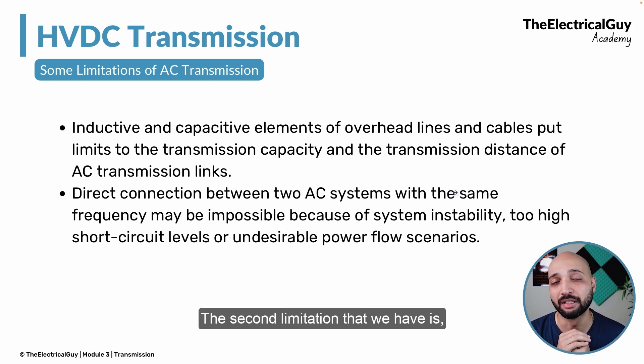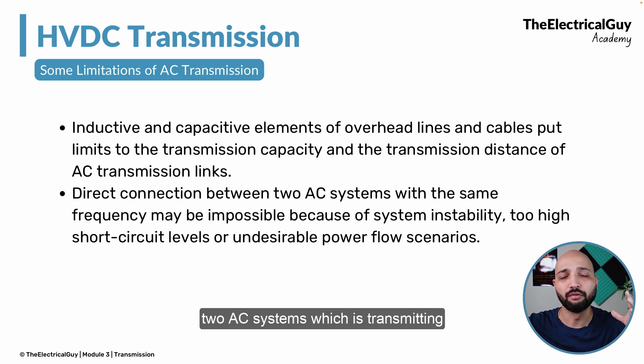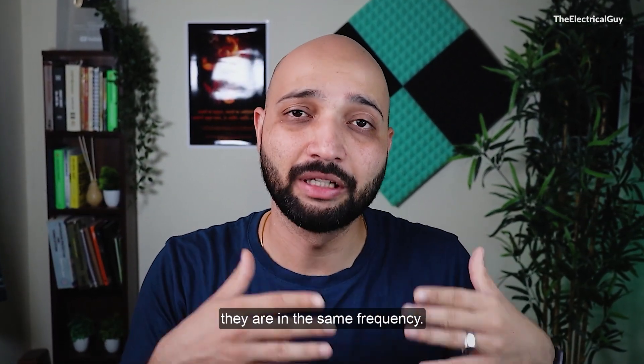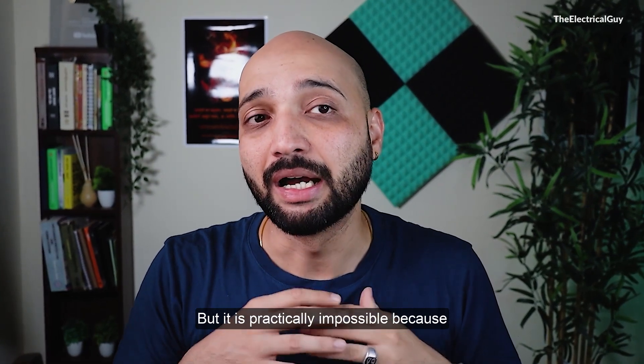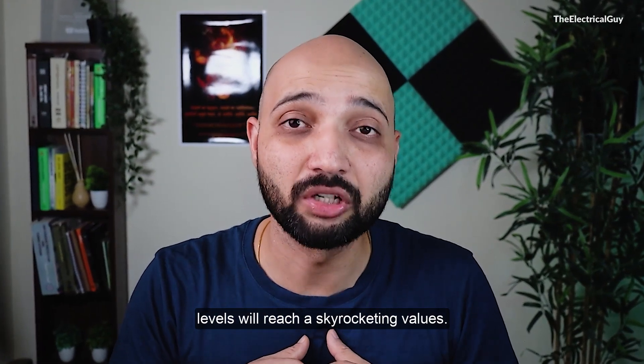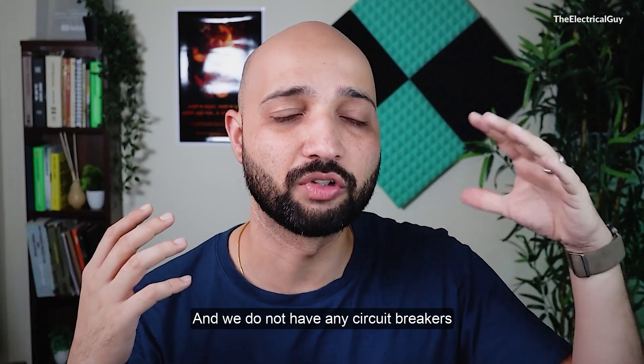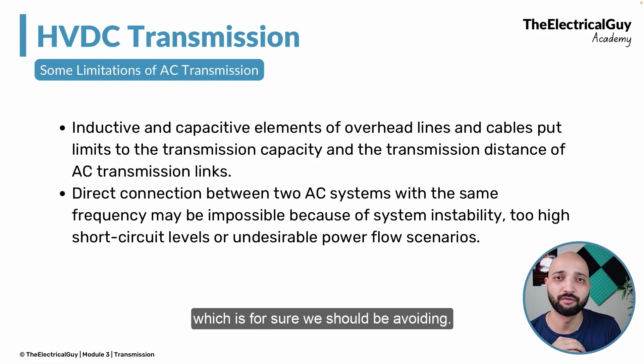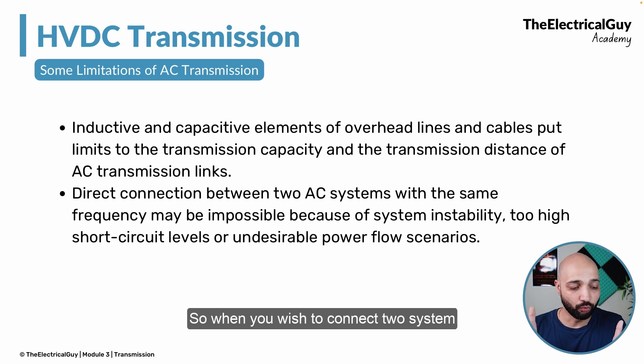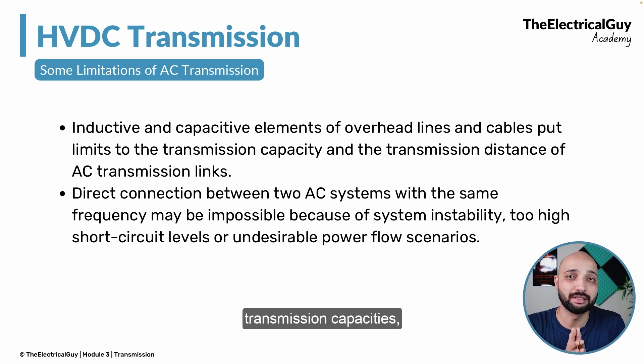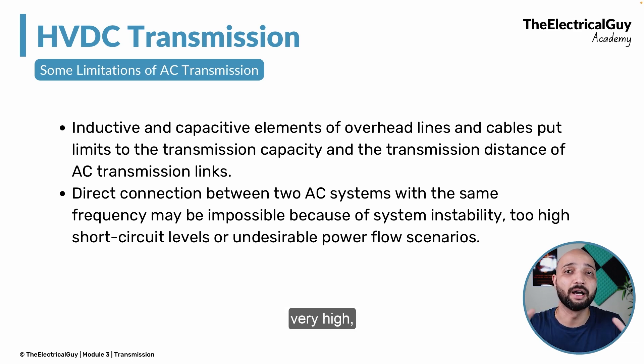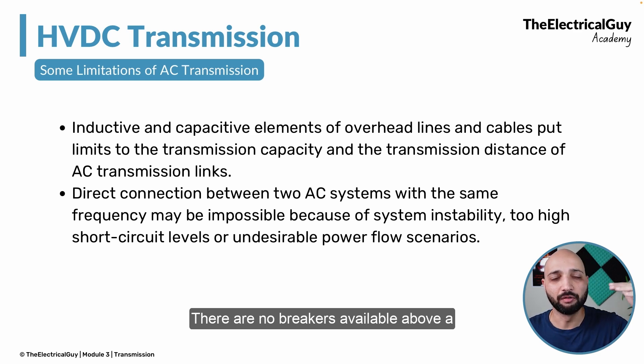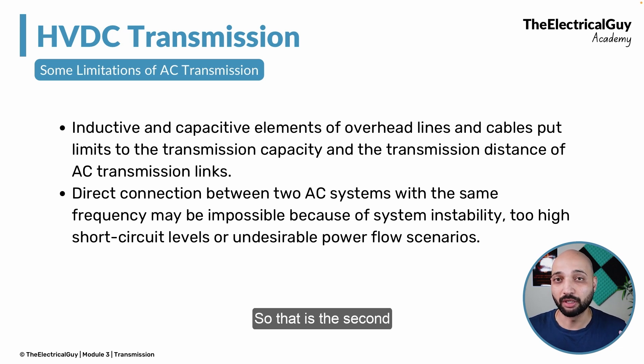The second limitation is that if you have two different AC systems transmitting bulk amounts of power and wish to connect them, it is practically impossible — even if they operate at the same frequency. This is because it is anticipated that short circuit levels will reach skyrocketing values, and we do not have any circuit breakers capable of breaking such high short circuit levels. It can also cause undesirable power flow scenarios.